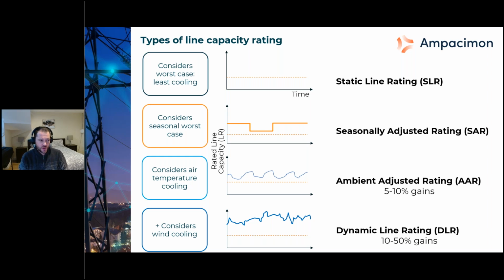Moving one step further, we get into what FERC Order 881 requires, and that is ambient adjusted ratings. And that is where you consider the temperature on the conductor. So the ambient temperature on the conductor, as I mentioned, is around 1% capacity improvement for every 1.8 degrees Fahrenheit change. So we can see that typically this has a pattern of day, night, day, night. In the day, the rating goes down. In the night, the rating goes up.